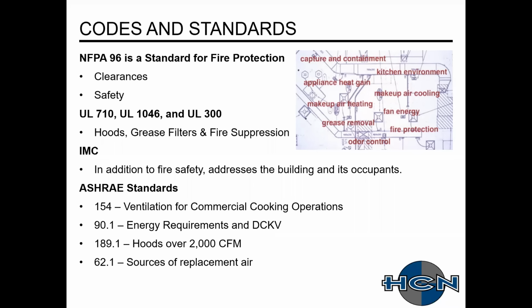So for hood stuff, the UL listings that are required for your hoods would be UL 710 for the hood itself. 1046 is for your filters. UL 300 for your fire suppression. Control panel, usually it's UL 508A. Power ventilators require UL 762. Those are your listings for those pieces of equipment.